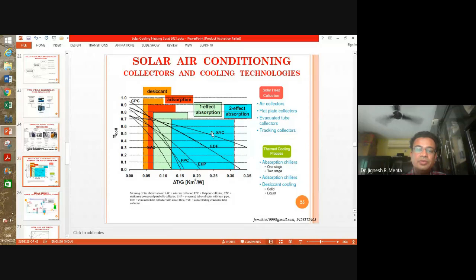So when you want to use a double effect absorption system, you choose your collector from here, right? Though they may be costlier, but efficiency wise they will be better. Then if you want to use single effect, you can go for a somewhat cheaper or more economical collector. Adsorption also requires a simpler collector, a comparatively low temperature collector, and desiccants also generally need comparatively low temperature collectors. So the collectors could be simpler in desiccant systems, adsorption systems and single effect absorption.